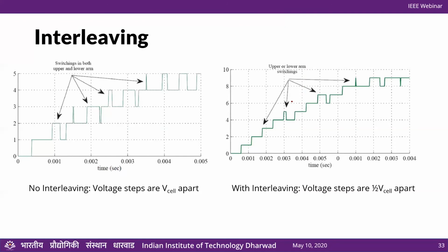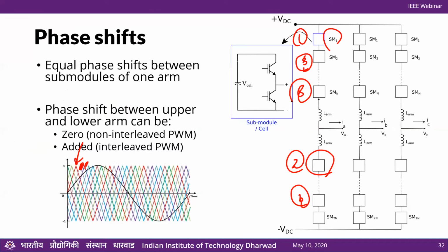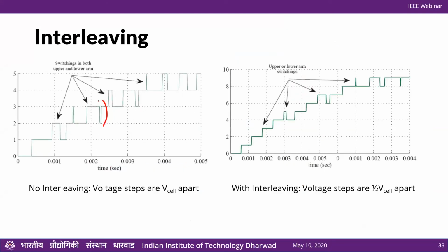When there's no interleaving, as a thought experiment, there will be one switching on the top arm and one switching on the bottom arm simultaneously, always. As a result, the voltage at node A will always experience a step equal to one module voltage. However, with interleaving, the step becomes half of the cell voltage. So interleaving is preferred: lower dV by dt, slightly better voltage profile, slightly better currents, lower harmonics, and so on.